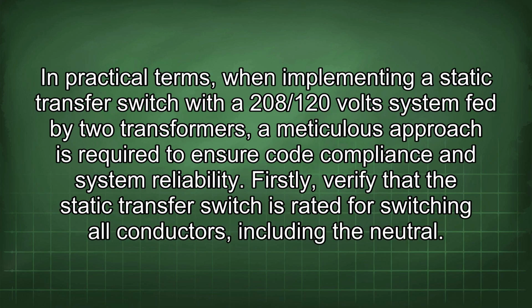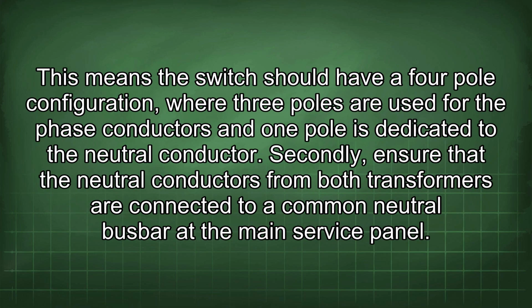In practical terms, when implementing a static transfer switch with a 208/120 volt system fed by two transformers, a meticulous approach is required to ensure code compliance and system reliability. Firstly, verify that the static transfer switch is rated for switching all conductors, including the neutral. This means the switch should have a 4-pole configuration, where 3 poles are used for the phase conductors and 1 pole is dedicated to the neutral conductor.